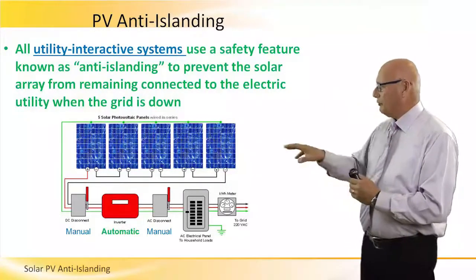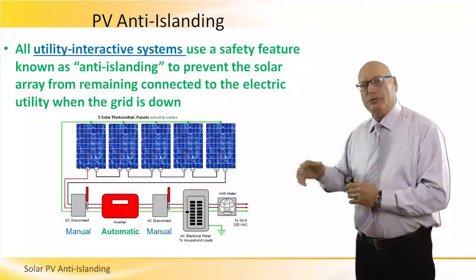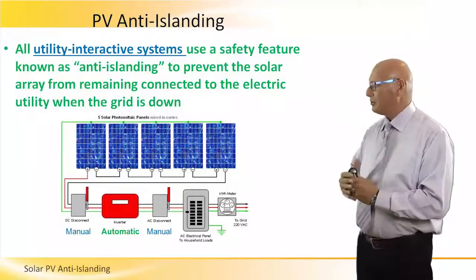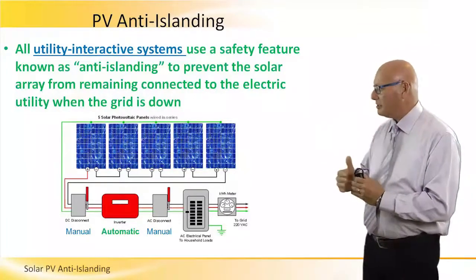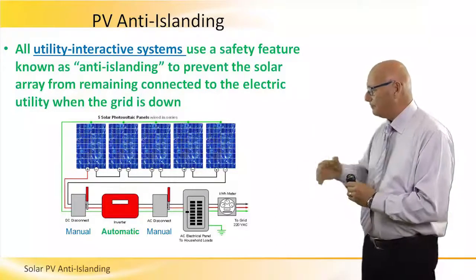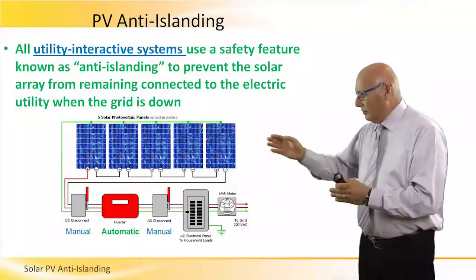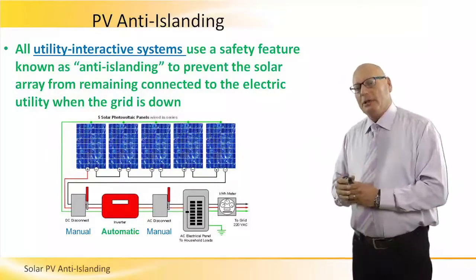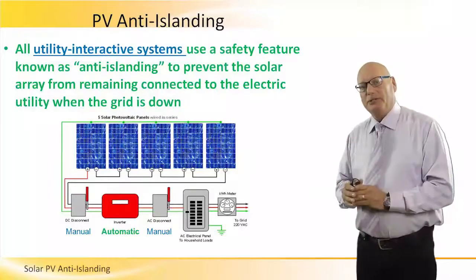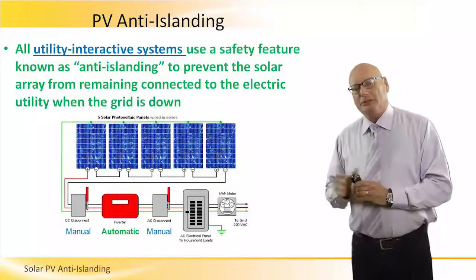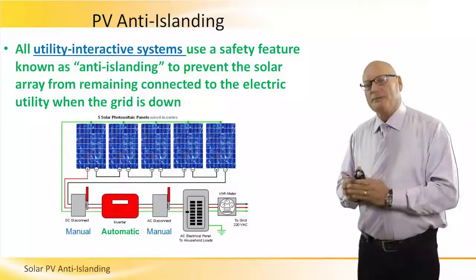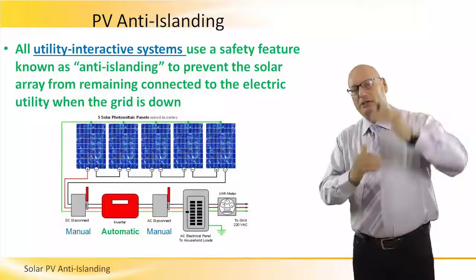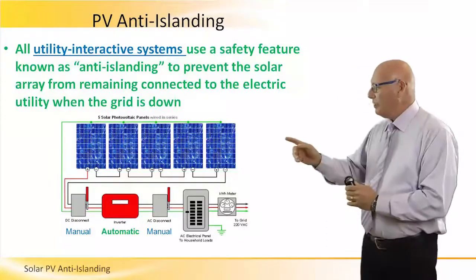In the picture at the bottom, we can see three levels of switching — three levels of disconnection — between the PV system at the top (the panels and arrays) and the grid on the bottom right. The first is an automatic one which takes care of anti-islanding, meaning that automatically when the grid is down, that device will shut down and cut the connection between the array and the grid. Then we have two manual disconnects.